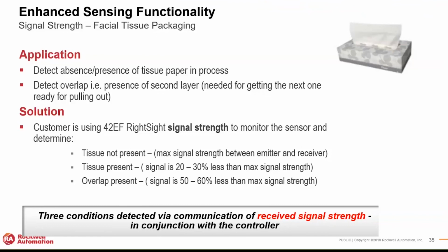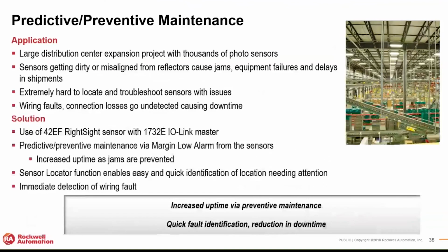We offered them that sensor, a diffuse sensor, which has more signal coming back from leather versus from cloth. Just a very inexpensive solution, and they will be implementing it. I did visit that plant. They had already tested by that time that the sensor can do the job. So there are more applications now that can be done as we are doing this with the received signal strength.